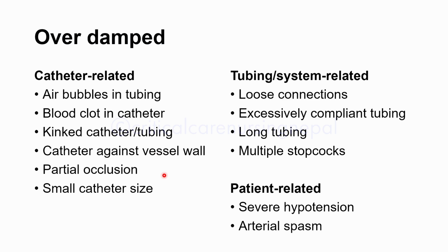So catheter related causes, there could be occlusions or obstructions because of air bubbles or blood clot in the catheter, or the tube has been kinked. This can all result in overdamping, showing no oscillations. And if the catheter is just against the vessel wall, it can have a partial occlusion, and a small catheter size will also lead to overdamping. And if there are loose connections, excessively compliant tubing, a very long tubing or multiple stopcocks, these can also lead to no oscillation, that means overdamping of the A line.